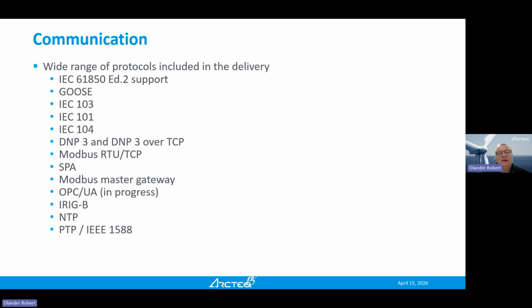So basically it means that you can connect our device directly to a SCADA system also, if you want, with the remote protocol. So that opens up quite many possibilities. DNP, Modbus, even the old Strömberg ABB protocol SPA we have. I think we are the only one still having it inside of the device. Modbus, we have also a Modbus gateway. So if you have other Modbus devices on your substation, you can connect them to our device for sharing the communication of those devices if needed in some place.